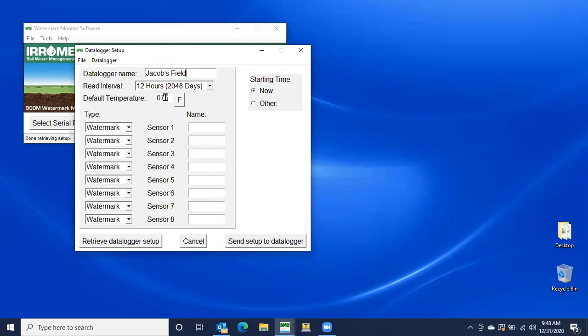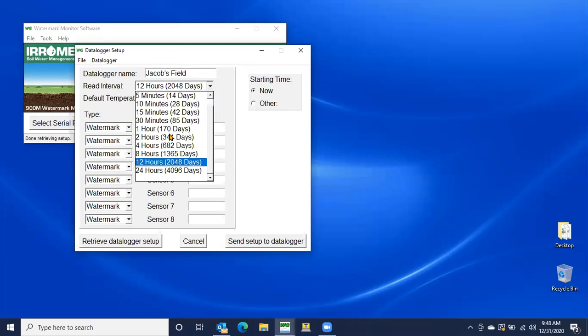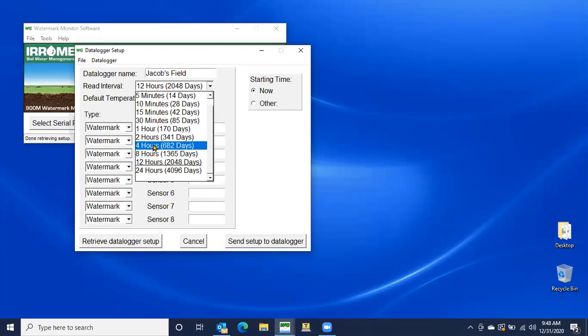The read interval, like I said, if you have a cellular, it's already programmed to one hour. If it's a manual version, I would go ahead and change it just to four hours just to get a little bit more data. It will hold about two years worth of data. So you're perfectly fine if you don't download it every week. But as I always say, I recommend checking these things out as frequently as possible because, hey, these are great tools and they give you a lot of good information.